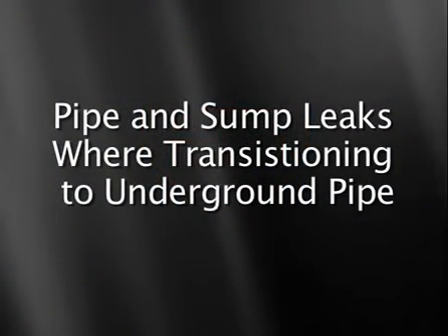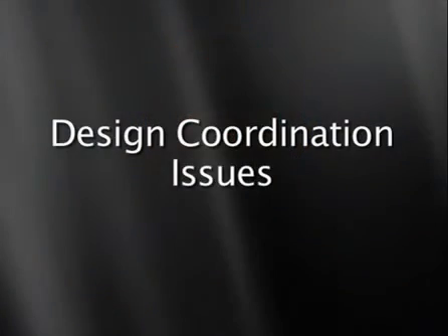While double-wall tanks provide protection for the tank contents, the tank equipment and piping connections are a source of fuel leaks that can be difficult to double contain. In some climates, a curbed area around the tank serves this purpose, or otherwise equipment can be mounted in a containment enclosure on the top of the tank. Above-ground tanks are sometimes used along with underground piping systems. The transition from underground to above-ground piping at the tank is commonly performed at a transition sump where the double wall systems may terminate and differing pipe materials can be joined.